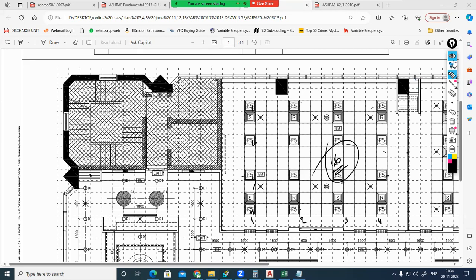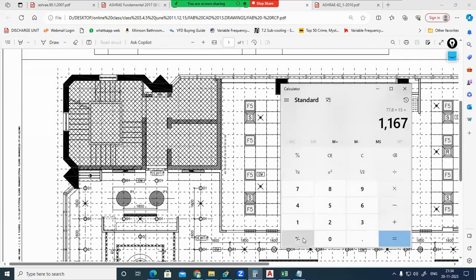So your total electrical load will be 16 into 39 watt per bulb. How much is it? 624. This only you should consider. But however much electrical load the lighting consumes, the same will enter the space as heat energy. Electrical energy converts into light energy, and light energy is radiation only. So however much power the lights consume, all of it will accumulate within the space as heat energy. So the entire lighting load you should consider, 624.